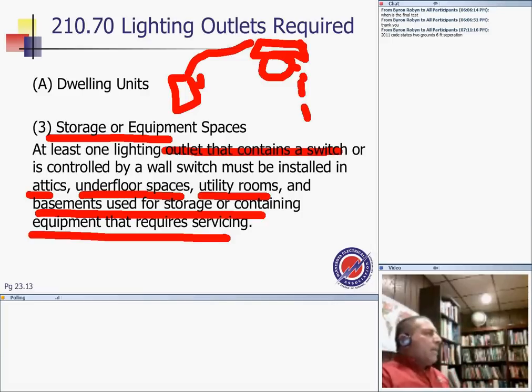Your lighting outlets can be a lighting fixture or can be a switched receptacle. One of the places in the NEC code book where we can't have a switched receptacle, as we all know, is the bathroom, kitchen, garages, and also unfinished basements. In these places you need a lighting fixture, basically. But in a bedroom, living room, or dining room, you can have a switched receptacle as your lighting outlet. Any question about switches, guys? Any question about switches?